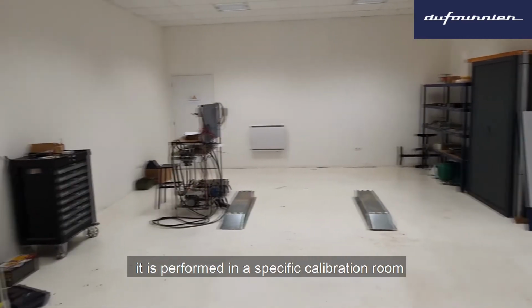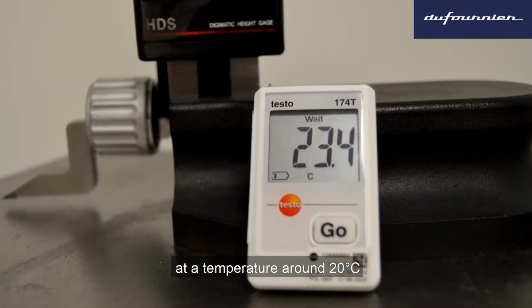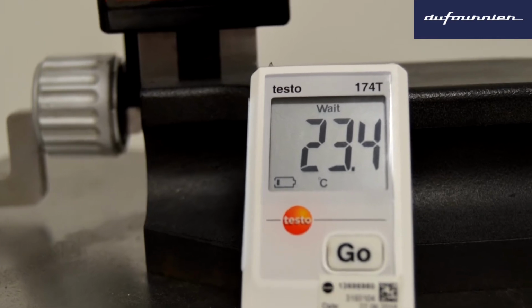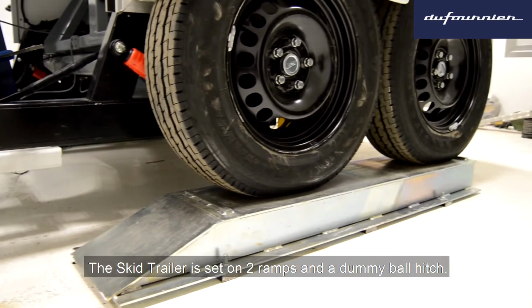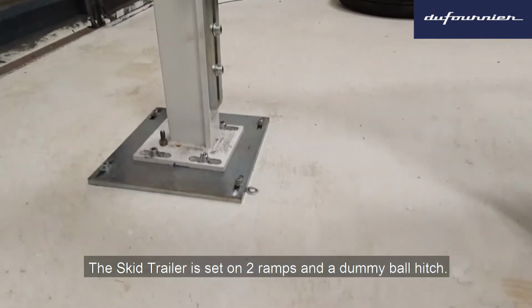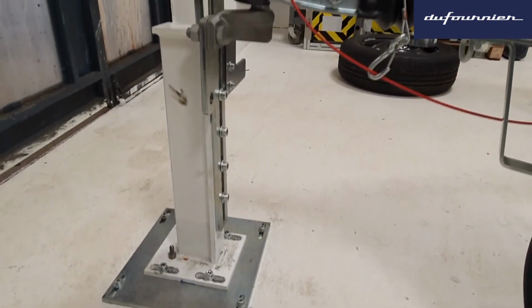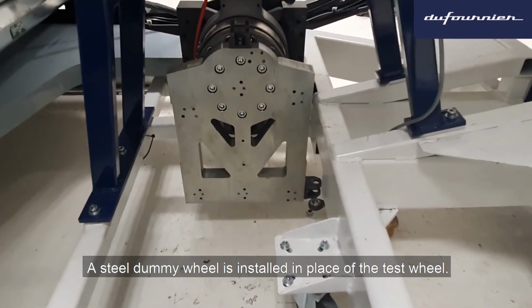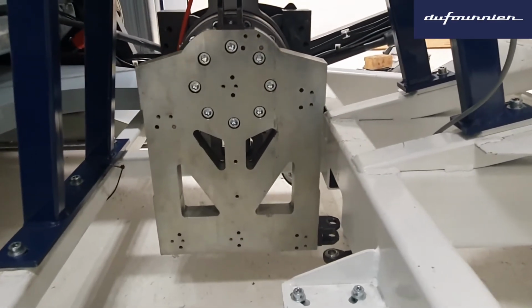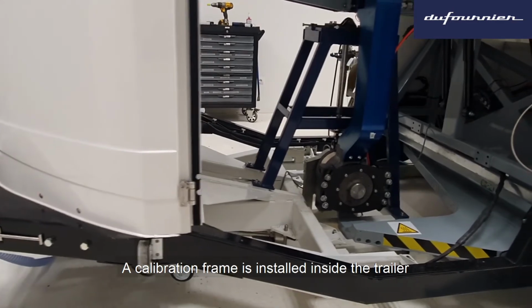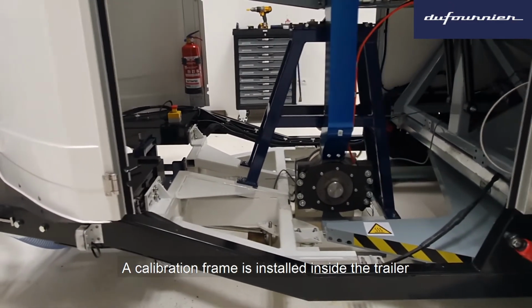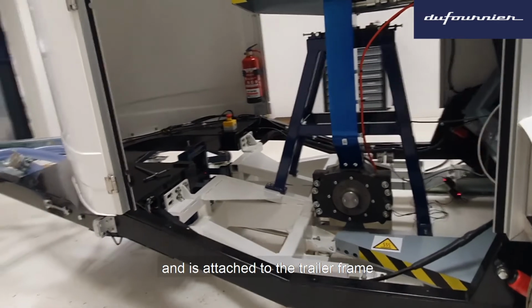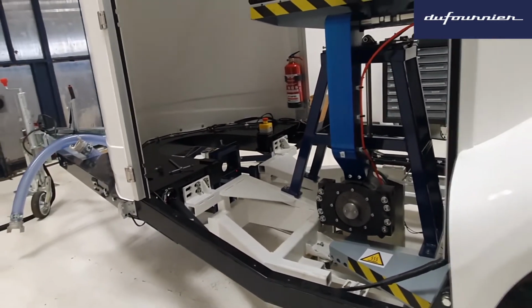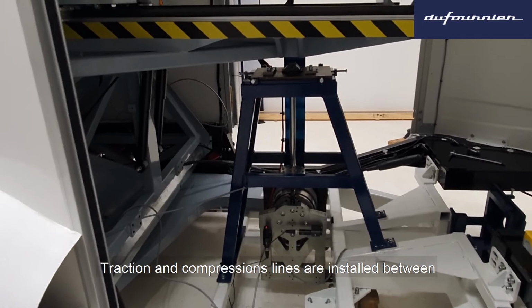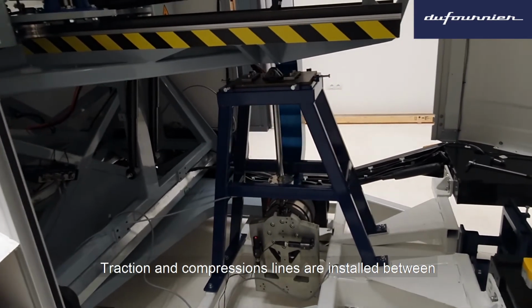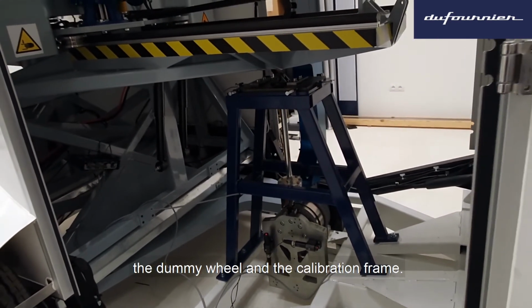It is performed in a specific calibration room at a temperature around 20 degrees. The skid trailer is set on 2 ramps and on a dummy ball hitch. A steel dummy wheel is installed in place of the test wheel. A calibration frame is installed inside the trailer and is attached to the trailer frame. Traction and compression lines are installed between the dummy wheel and the calibration frame.